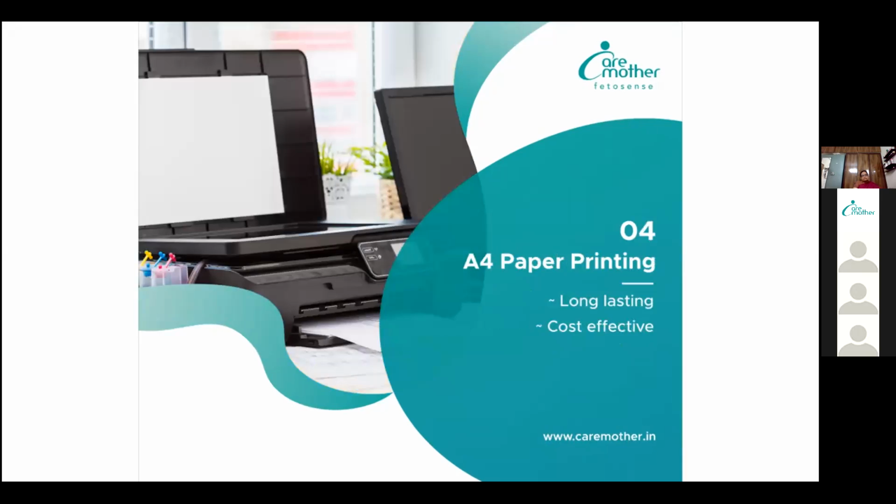The next thing is this device prints on normal A4 paper. It doesn't require a thermal CTG roll. So basically the printing cost comes down. Also, an A4 print is more durable compared to thermal paper, which fades after a point in time. And as ma'am showed you, there will be a QR code in the print of the test, which the mother can use to download a mother's app, wherein she'll be able to hear the baby's heartbeat sound after the test is done.